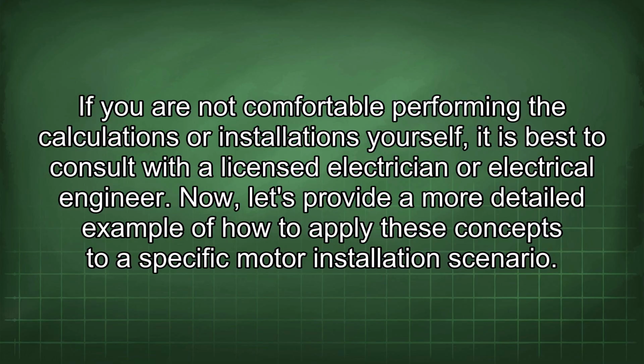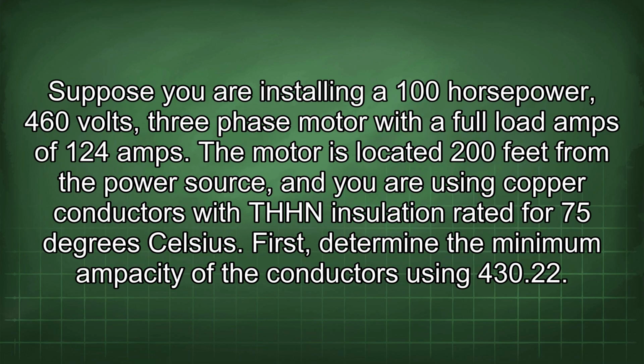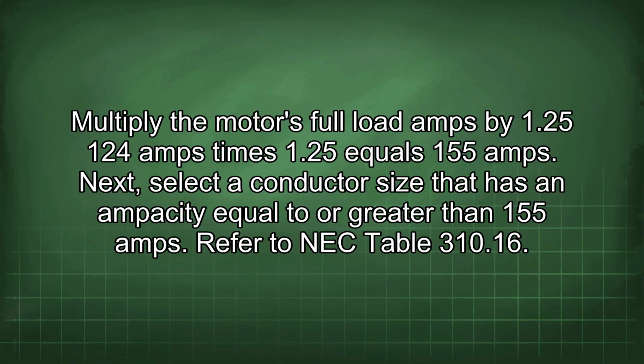Now let's provide a more detailed example of how to apply these concepts to a specific motor installation scenario. Suppose you are installing a 100 horsepower, 460 volt, three-phase motor with a full load current of 124 amps. The motor is located 200 feet from the power source, and you are using copper conductors with THHN insulation rated for 75 degrees Celsius. First, determine the minimum ampacity of the conductors using 430.22. Multiply the motor's full load amps by 1.25. 124 amps times 1.25 equals 155 amps.